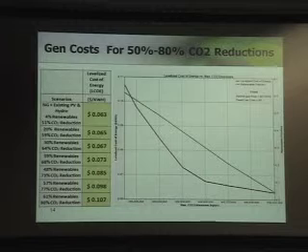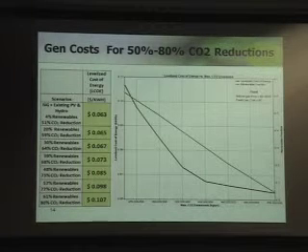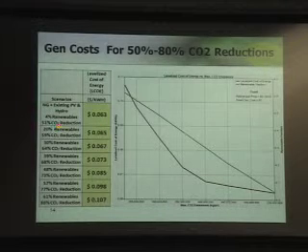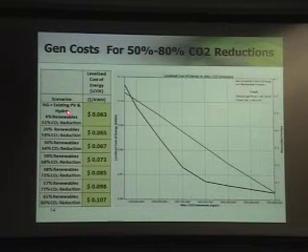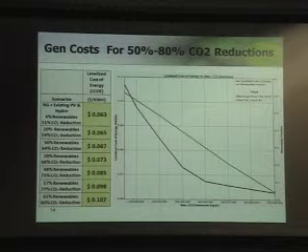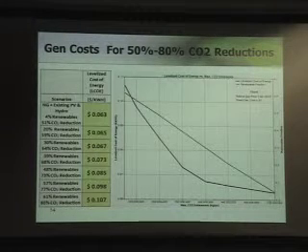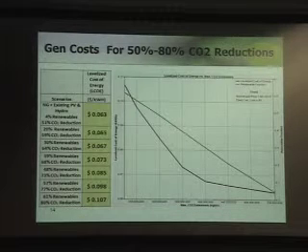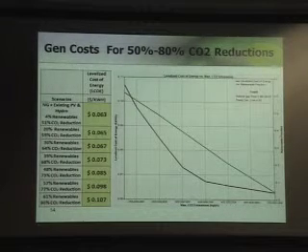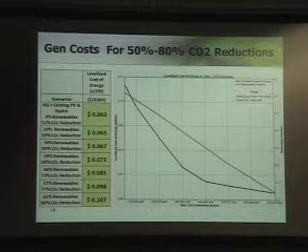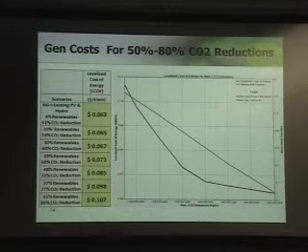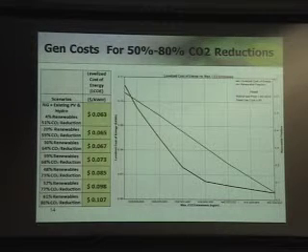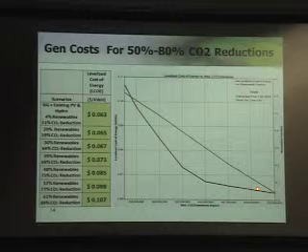Punchline time. Let's talk about what the numbers come out as. Cost of generation for 50% carbon reduction with a natural gas grid is 6.3 cents a kilowatt hour. This has no cost of anything except for running the plants, the fuel for the plants, the operation and maintenance for the plants, and the transmission costs for the wind that comes in, and purchasing all of the capital. So all the plant costs are figured in here, amortized over 25 years. All the upfront costs are in, and that's the curve I just showed you.